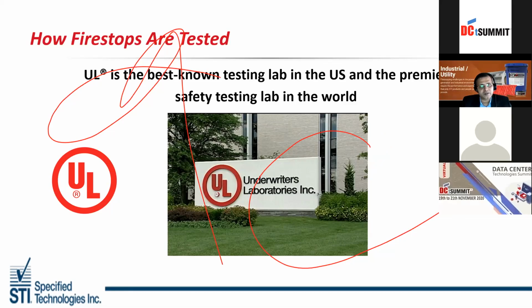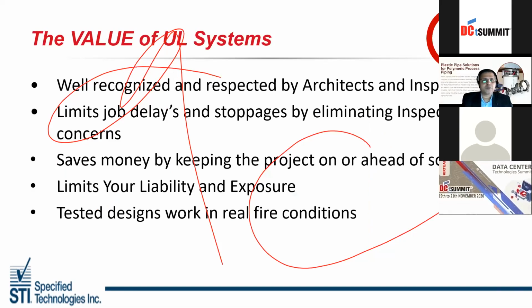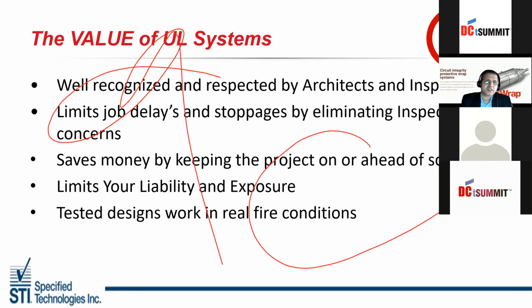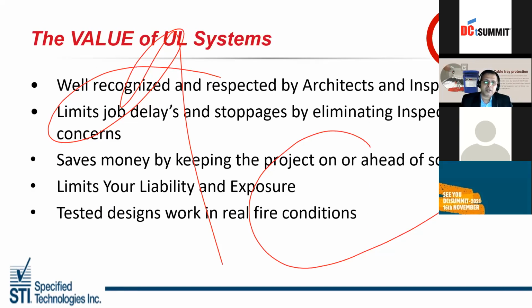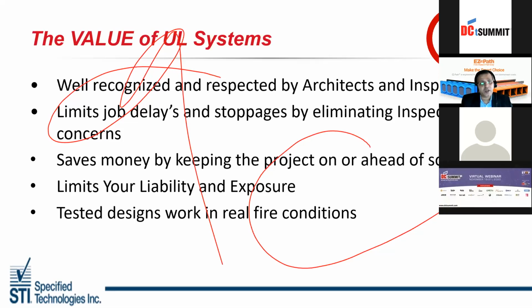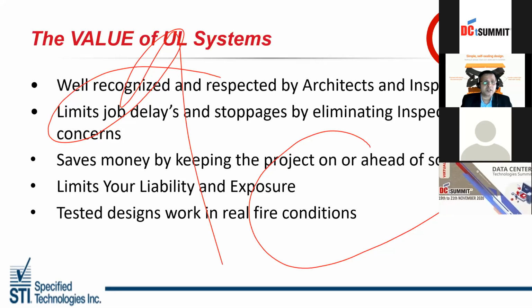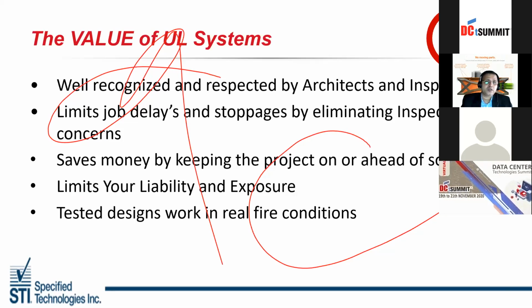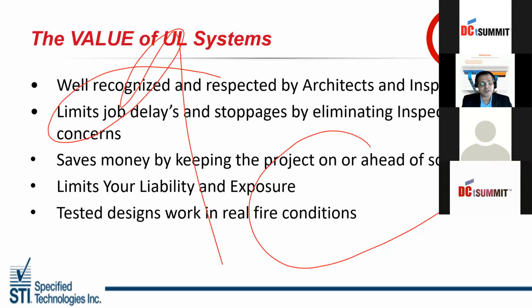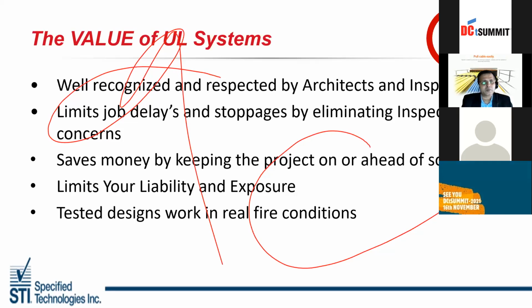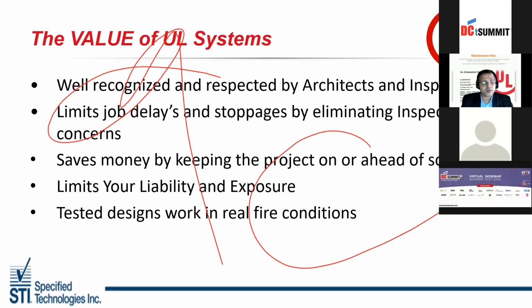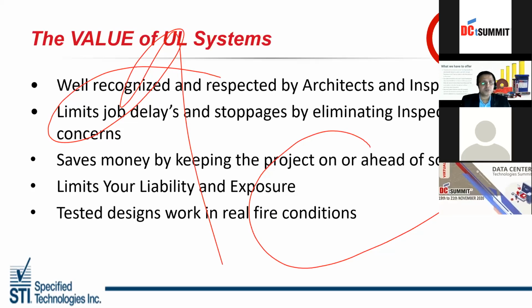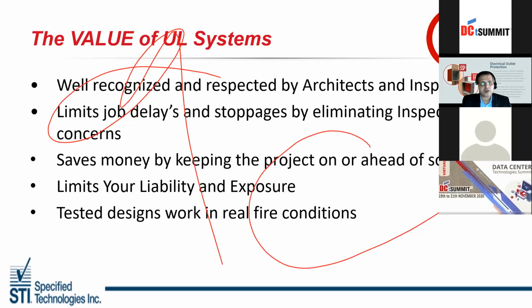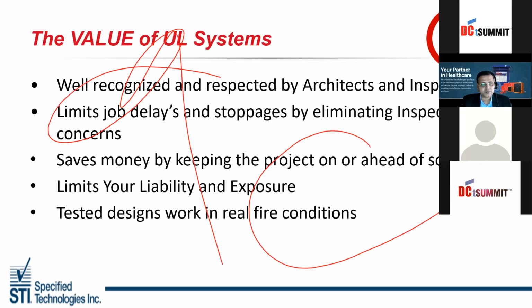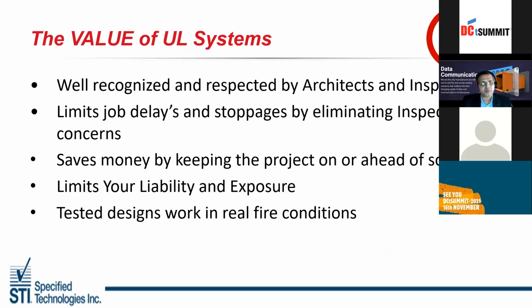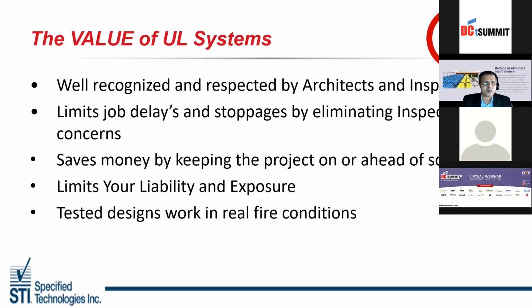The reason for the value of UL is that it is well recognized and respected by architects and inspectors. It limits job delay, like if there are scenarios wherein you have multiple penetrations or two combustible pipes passing through the same opening. All this has to be tested, and UL has done the testing over so many years. They have all these testing standards in place. So when a fire stopping person submits the document, it limits the delay, because once the site survey has been done and the submittal has been submitted, any delay would stop the work.